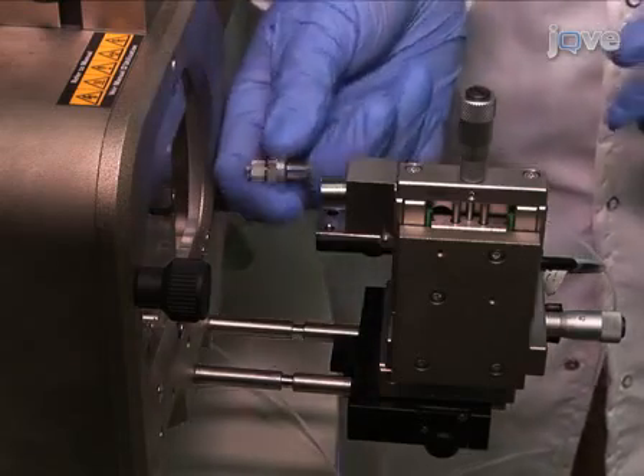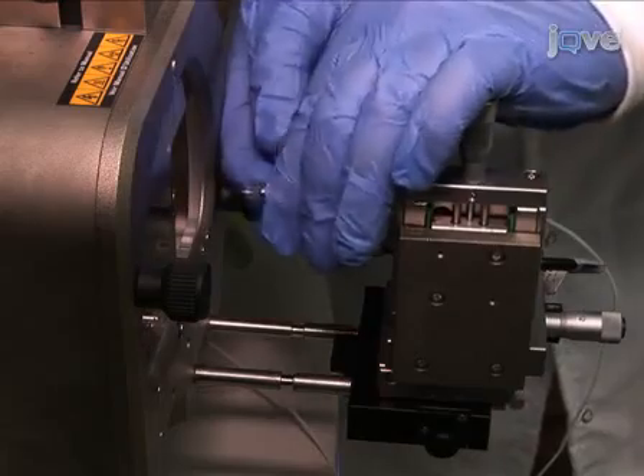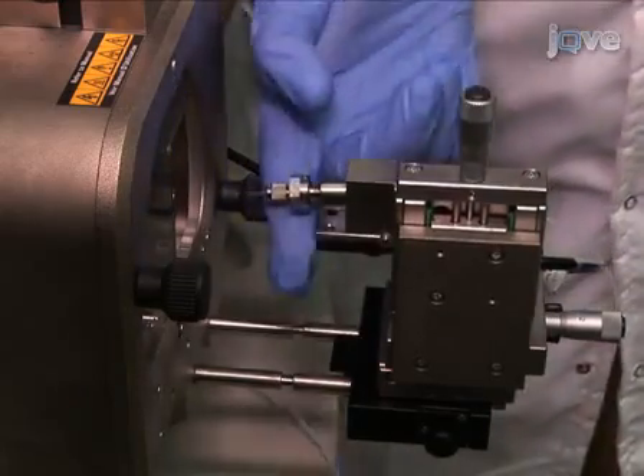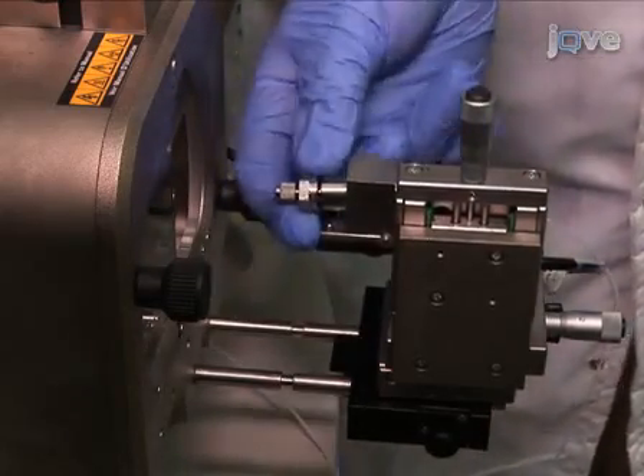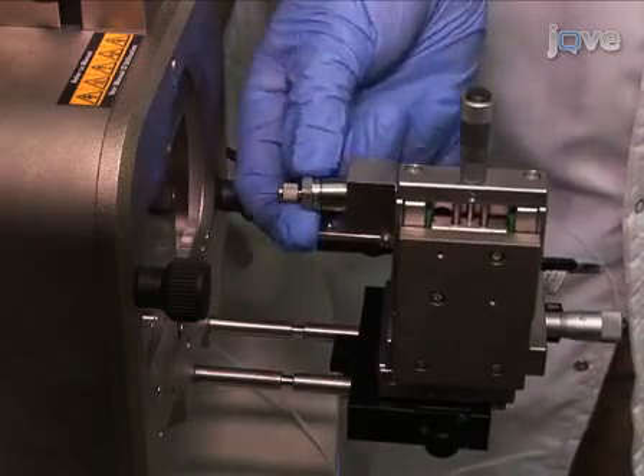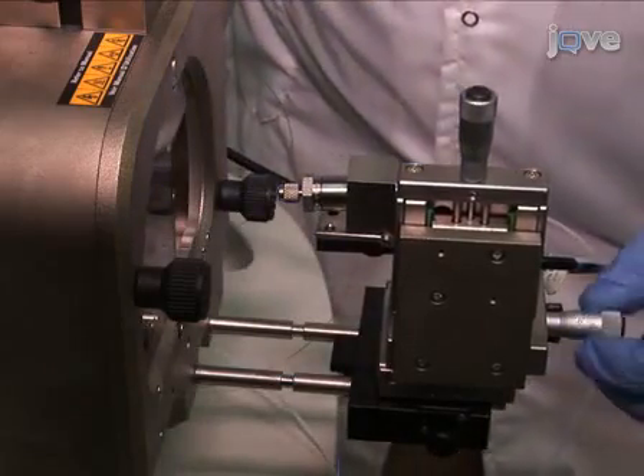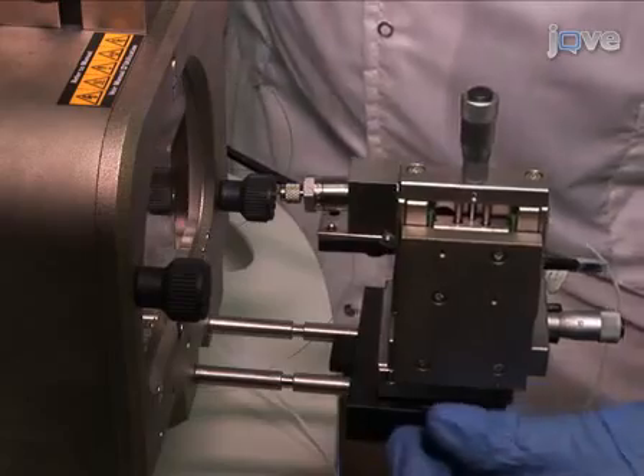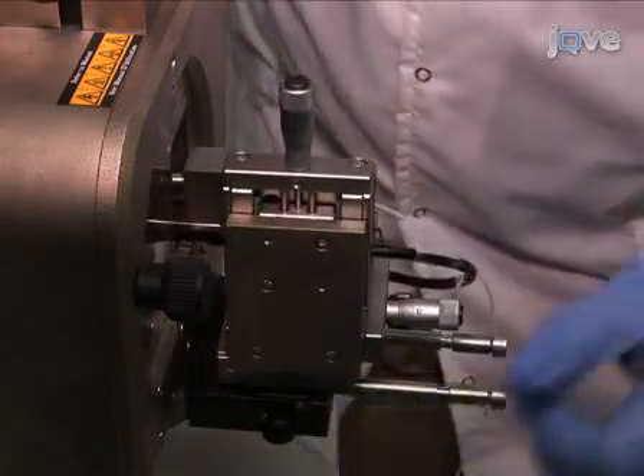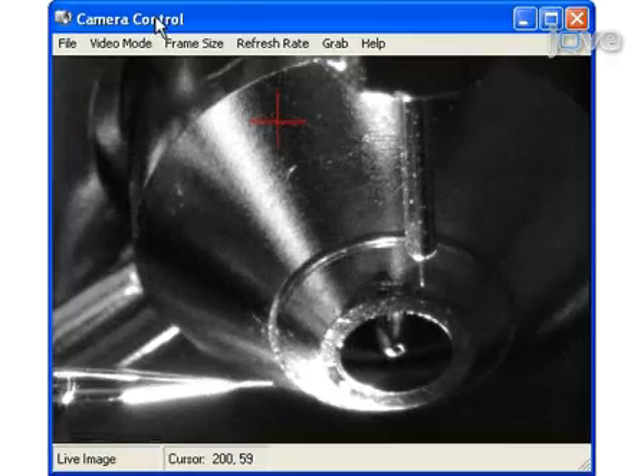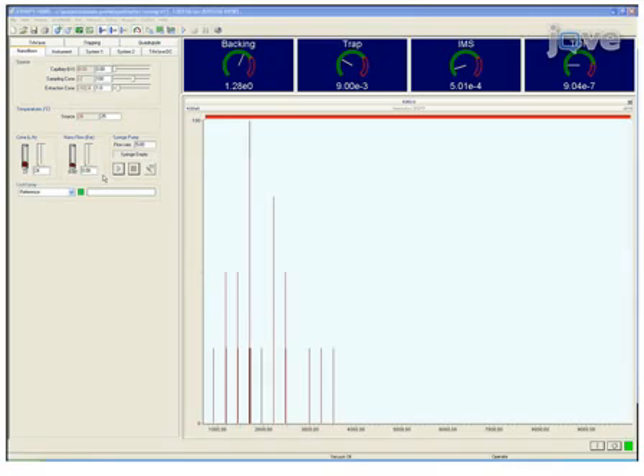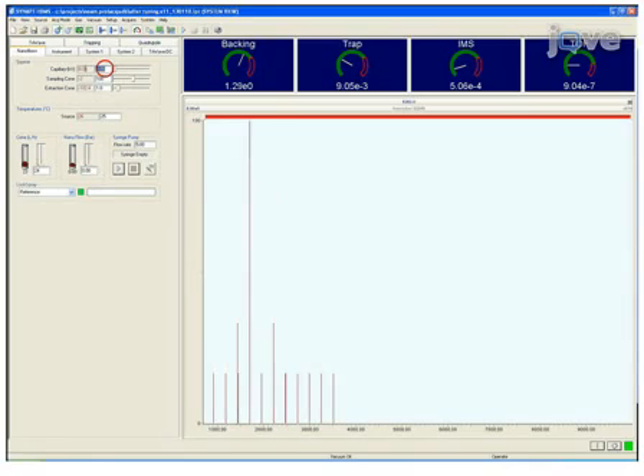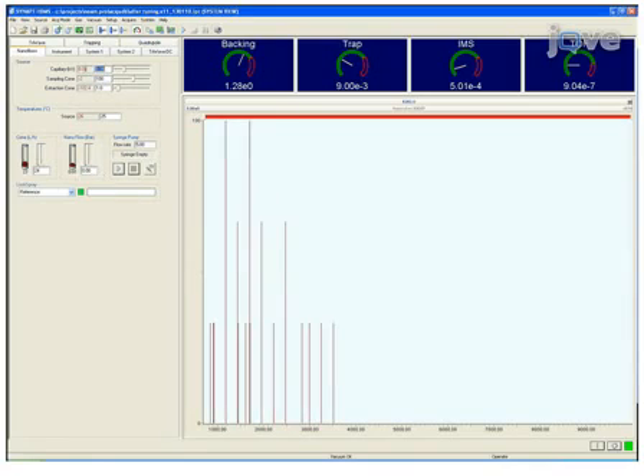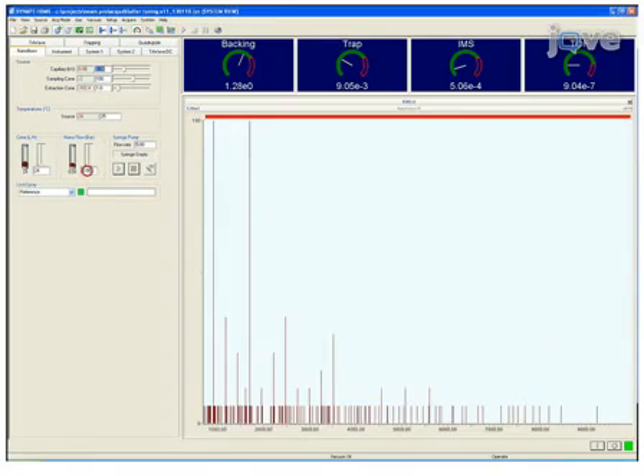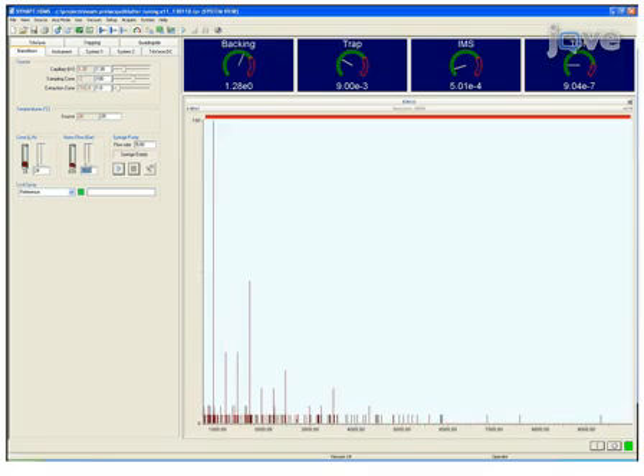Next, connect the capillary holder to the NanoFlow ESI interface. Rotate the XYZ stage backwards to avoid damaging the capillary and push the stage into its activated position. The capillary should be placed at a 1 to 10 mm distance from the cone orifice. Apply capillary voltage and low nanoflow pressure until spray is initiated. Then try to reduce the nanoflow pressure to a minimal value.